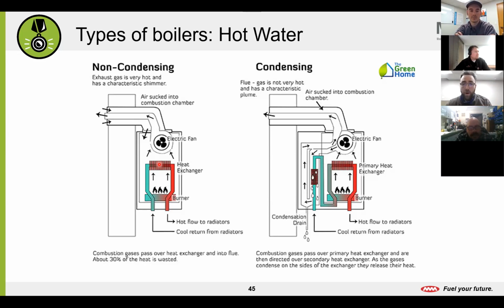With condensing though, the big difference is there's actually a second heat exchanger. We actually call it a secondary heat exchanger. So if we look at our picture here, we have our primary, just like our standard efficiency or non-condensing boiler, and the water is absorbing heat from that. But then we continue on to actually a secondary heat exchanger there, and that water will still continue to absorb the heat content out of this flue gas.